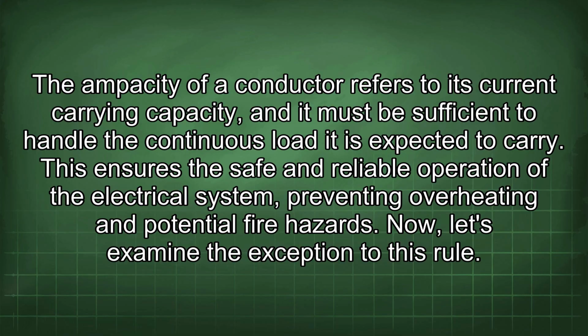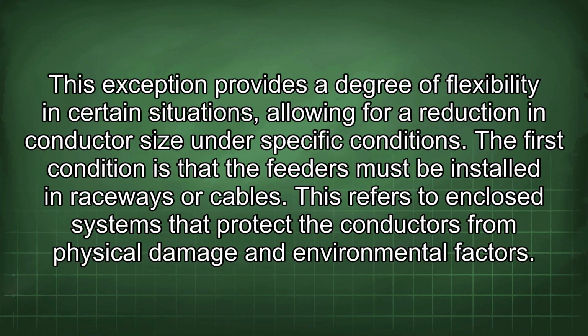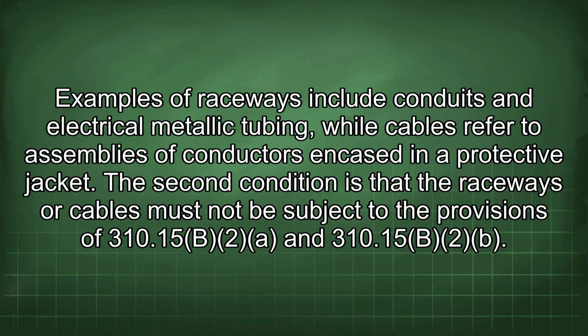Now, let's examine the exception to this rule. This exception provides a degree of flexibility in certain situations, allowing for a reduction in conductor size under specific conditions. The first condition is that the feeders must be installed in raceways or cables. This refers to enclosed systems that protect the conductors from physical damage and environmental factors. Examples of raceways include conduits and electrical metallic tubing, while cables refer to assemblies of conductors encased in a protective jacket.